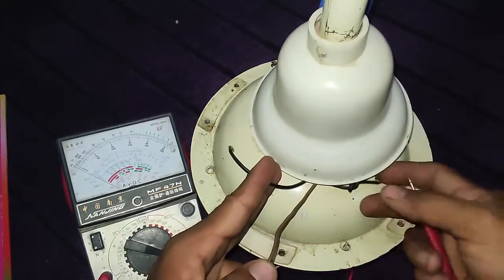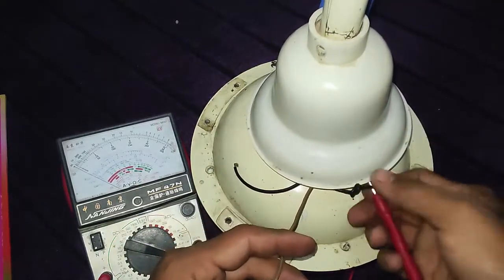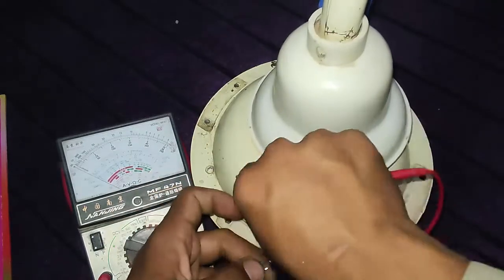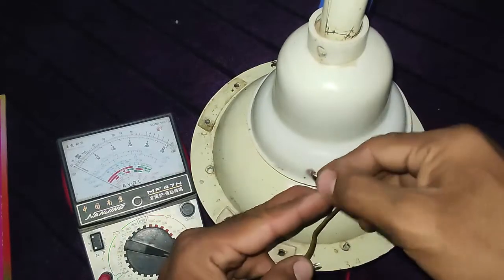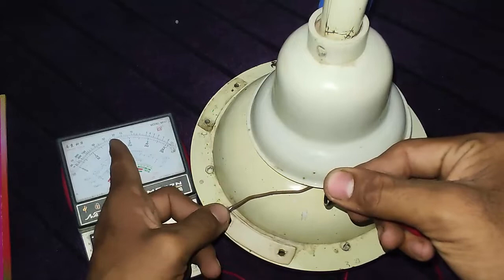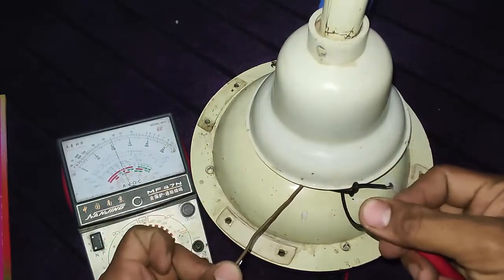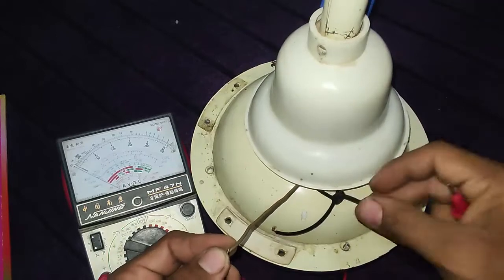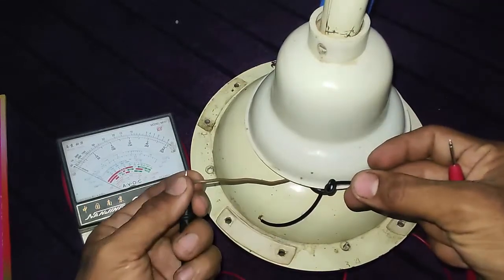If I test with this, it's almost 16 ohms, and if I test with this, it shows 20 or 25 ohm resistance. So this is starting, this is running, and this is common: common, start, and run.